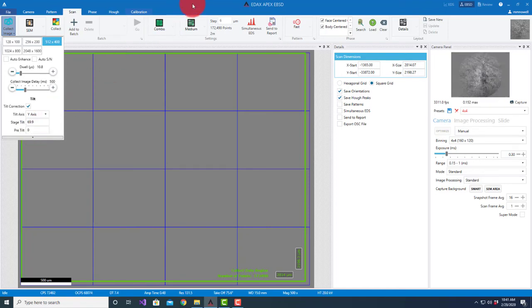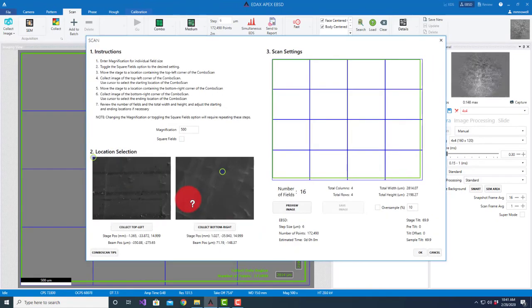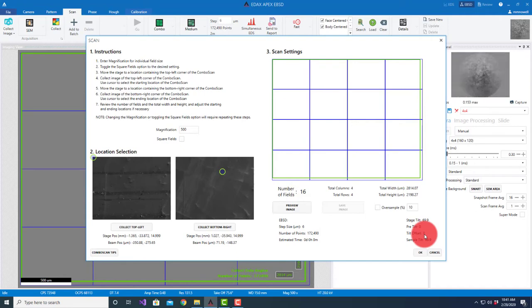I'm going to click this back to bring this back up. The tilt offset is a value that we can adjust to say if our pre-tilted holder is 70 degrees but the way we mounted the sample it's a little bit off, so we have to put in a little adjustment factor. I'm going to run mine based on the fact that I think my sample is at the actual stage tilt. But to get the best results, sometimes you'll check the actual sample tilt or you have a holder that puts it in the exact plane.